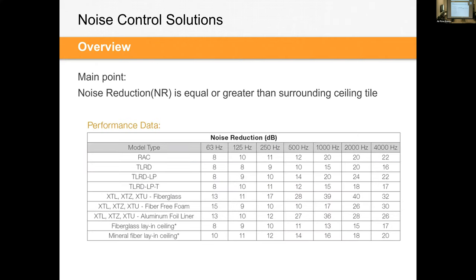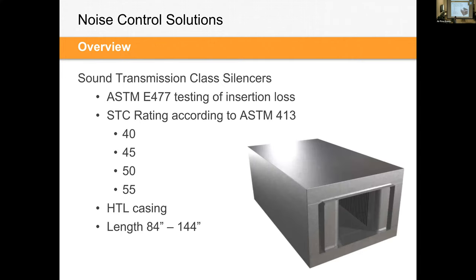What we've done is develop these products to either meet or exceed the same transmission loss as a fiberglass or mineral fiber ceiling tile. And you can see the return air canopy here, 8, 10, 11, and so on, is very similar to that of a fiberglass ceiling tile. So putting that canopy over top of your return grill effectively makes it work similar to the surrounding ceiling tiles, like you were alluding to. Now, instead of some giant heavy gauge elbow, it's a very lightweight, low-cost solution to increase your ceiling effectiveness. We talked about this a little bit earlier.